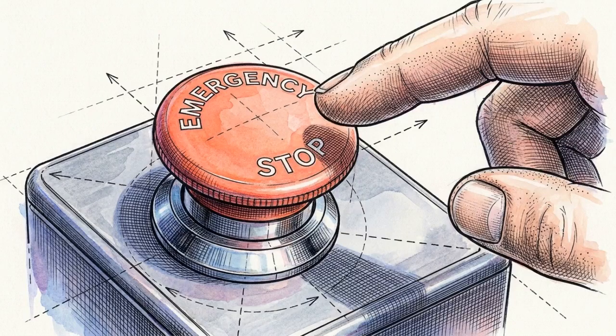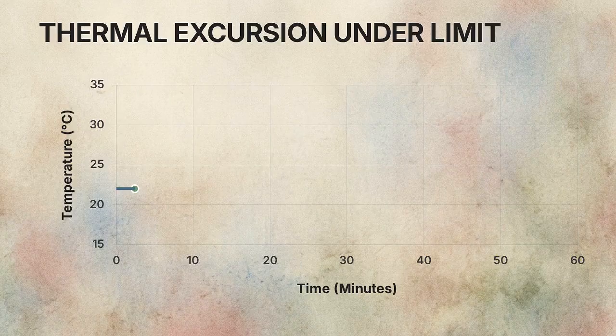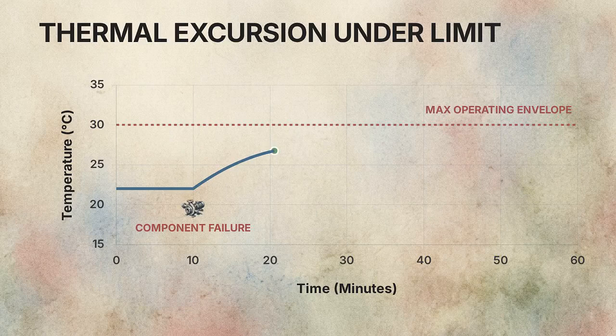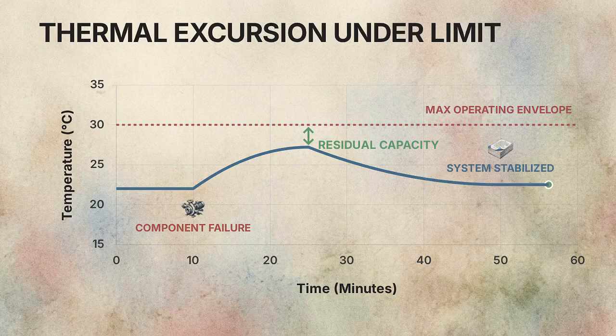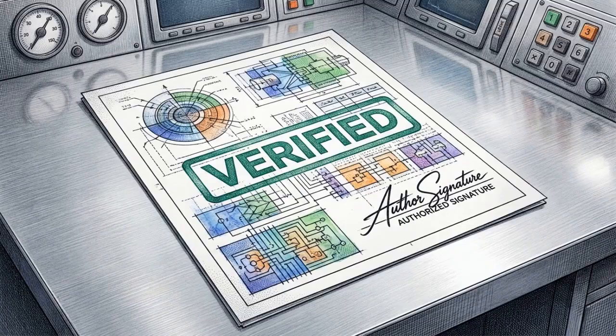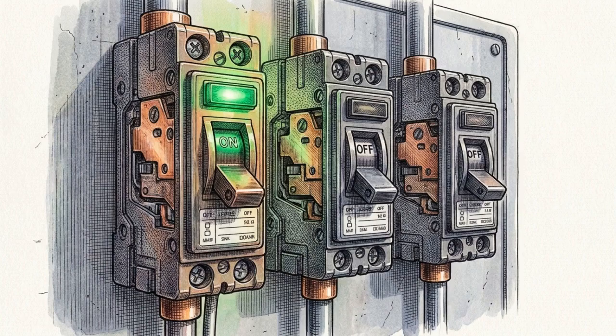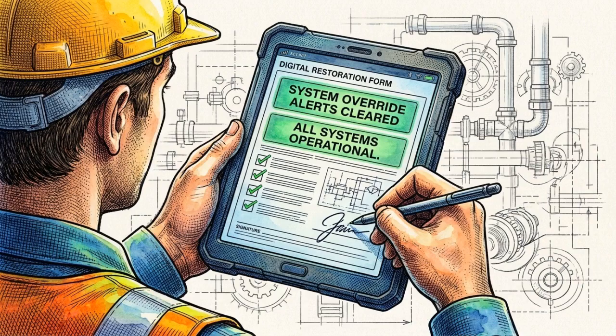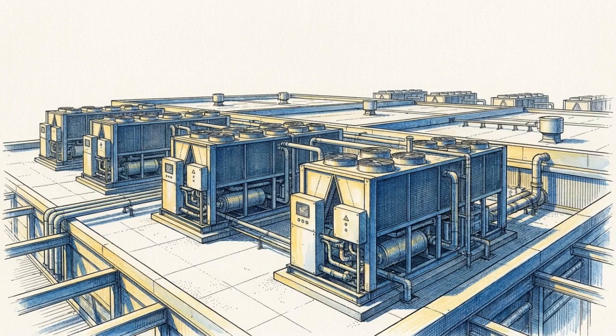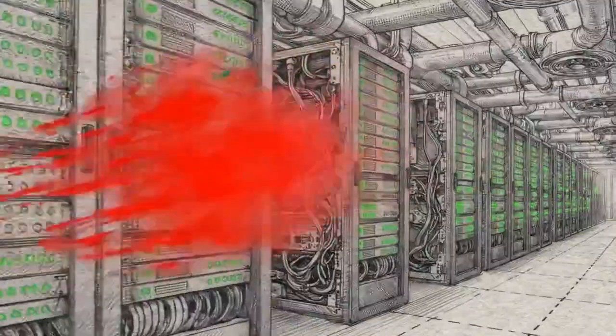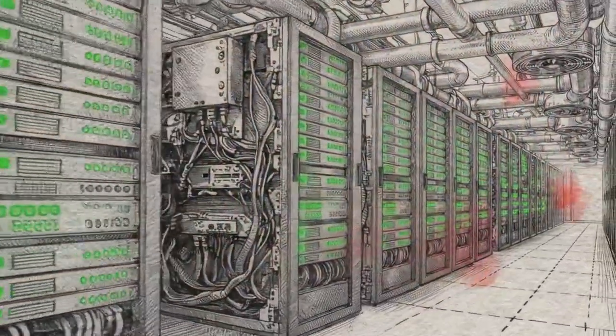At level 5, the integrated systems test, operators intentionally initiate controlled failures. They verify the automatic response of the mechanical loop, track residual capacity limits, and confirm that temperature excursions stay within the declared operating envelope. Surviving the failure requires a strict restoration proof. Operators must return the system back online one controlled step at a time, confirm standby availability, clear all manual overrides, and formally sign off on the restoration record. The true purpose of this entire commissioning sequence is not to verify that a chiller runs on a sunny day. It exists to definitively prove the system's ability to survive and recover from cascading failure under maximum IT stress.